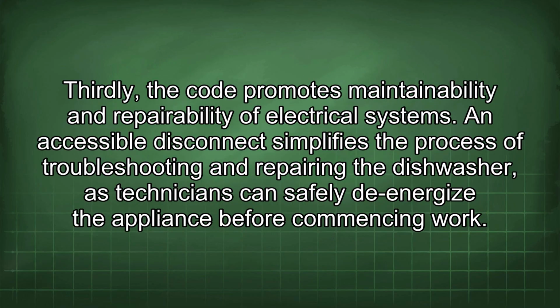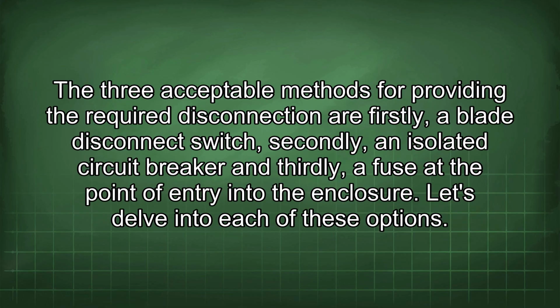Thirdly, the code promotes maintainability and repairability of electrical systems. An accessible disconnect simplifies the process of troubleshooting and repairing the dishwasher, as technicians can safely de-energize the appliance before commencing work. The three acceptable methods for providing the required disconnection are firstly, a blade disconnect switch, secondly, an isolated circuit breaker, and thirdly, a fuse at the point of entry into the enclosure. Let's delve into each of these options.